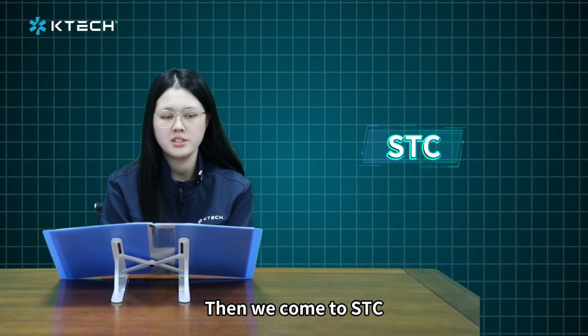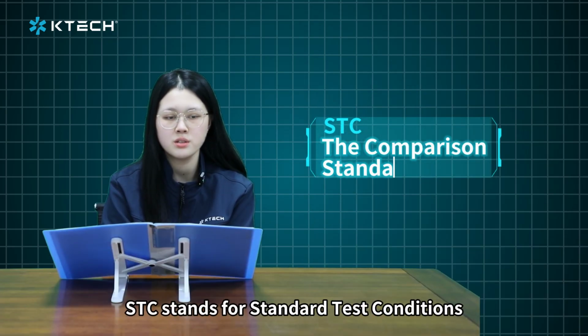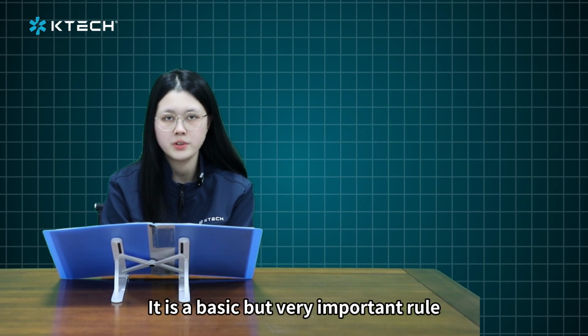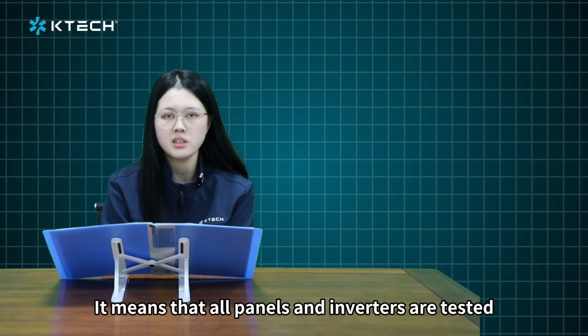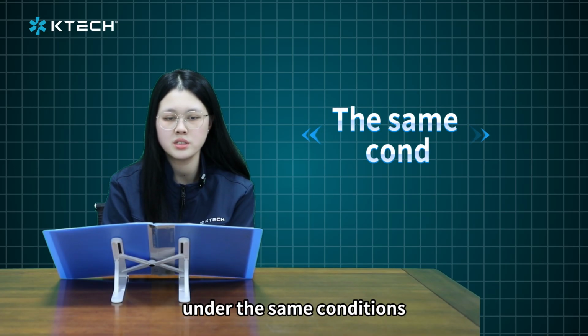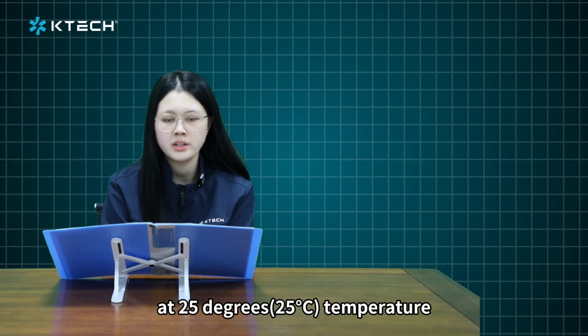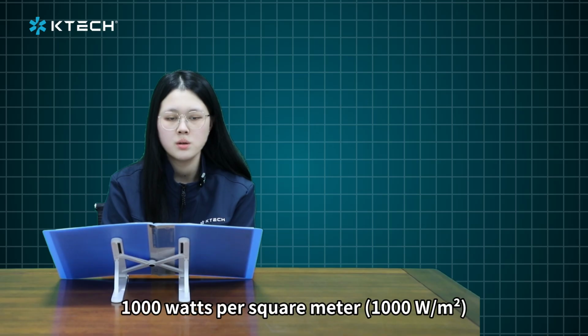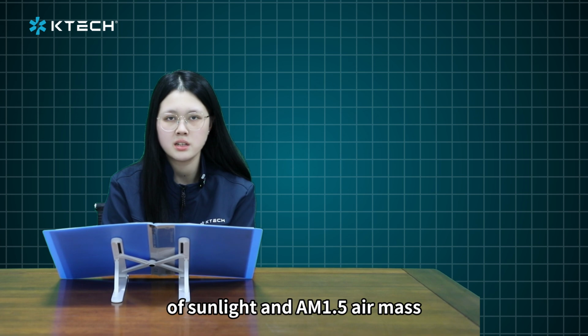Then we come to STC. STC stands for Standard Test Conditions. It is a basic but very important rule. It means that all panels and inverters are tested under the same conditions at 25 degrees Celsius temperature and 1 kilowatt per square meter of sunlight and AM 1.5 air mass.